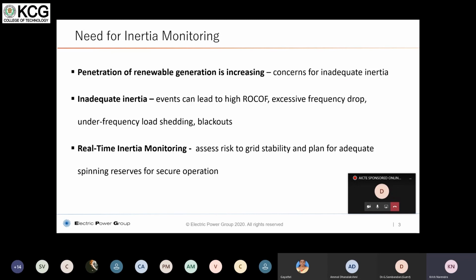In terms of wind, even though it has rotating masses through the big windmill blades that can store kinetic energy, unfortunately the design is such that it is not allowed to put its energy back to the grid. So none of these renewables integrated into the grid are able to support the inertia of the system. Therefore, as the penetration of renewable generation increases, there is a huge concern of inadequate inertia in the system.